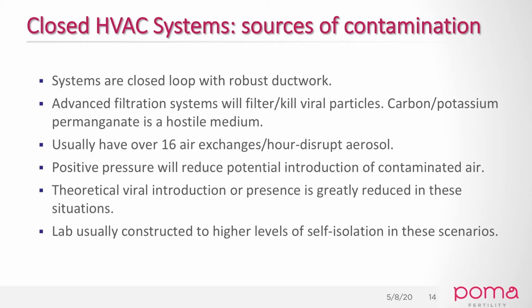Comparing the two, closed HVAC systems have robust ductwork to handle increased pressure, plus advanced filtration using carbon and potassium permanganate, which is a hostile medium for viruses and tends to kill them. Air exchanges are usually 16 to 18 per hour, effectively disrupting any theoretical aerosol in the lab. The positive pressure in these rooms reduces the potential for contaminated air to enter, so theoretical viral introduction is greatly reduced in labs built with self-isolation and positive pressure in mind.